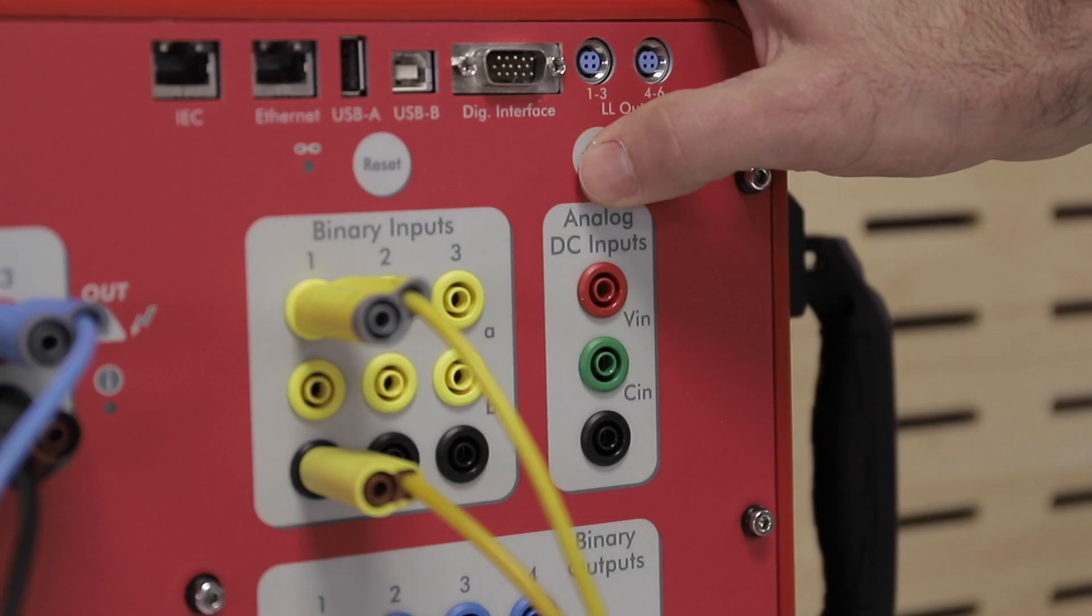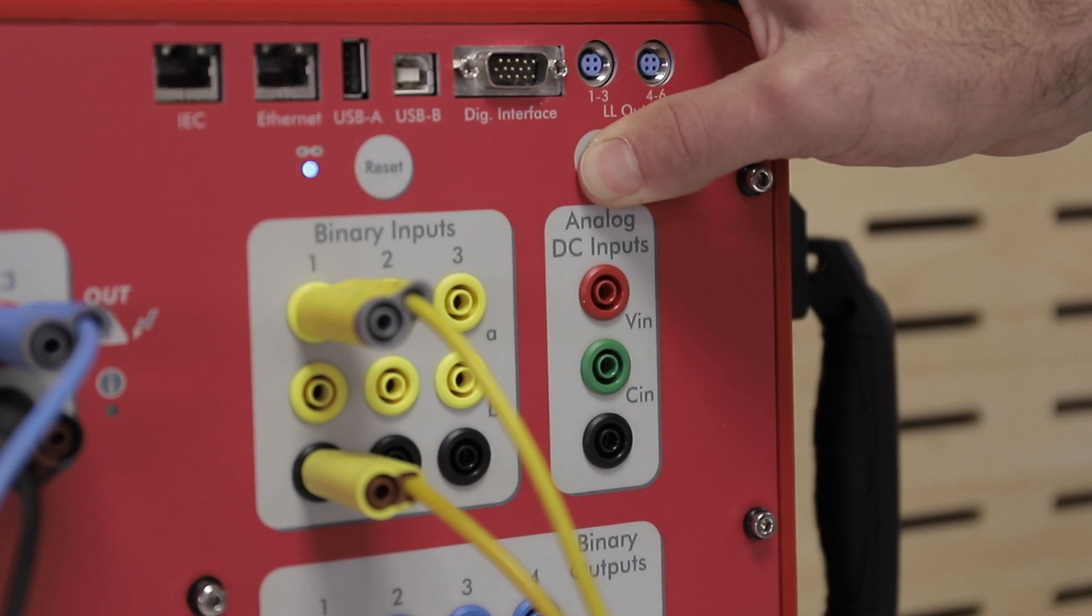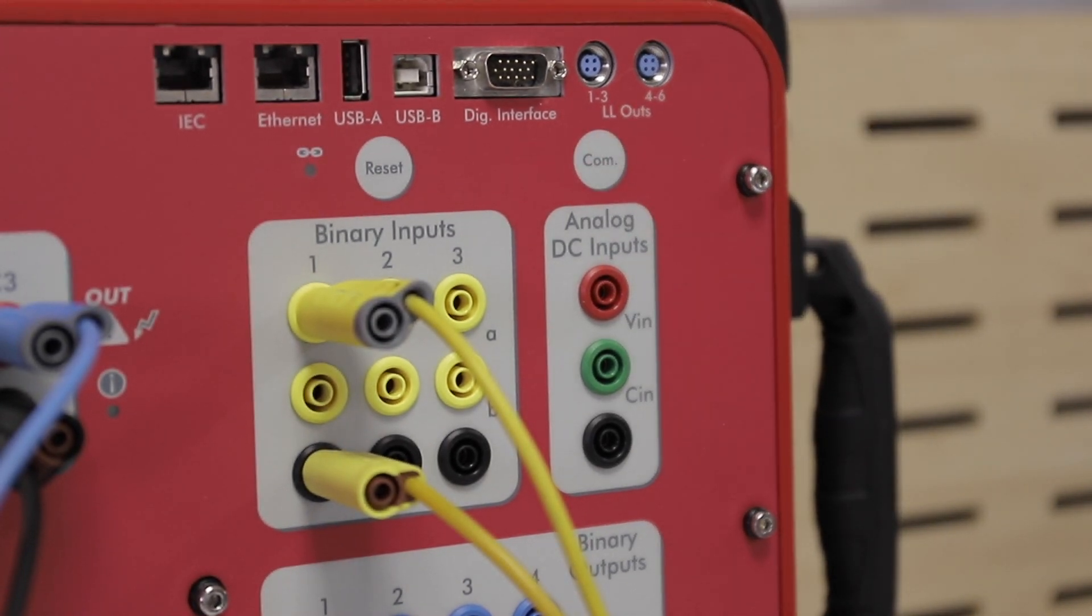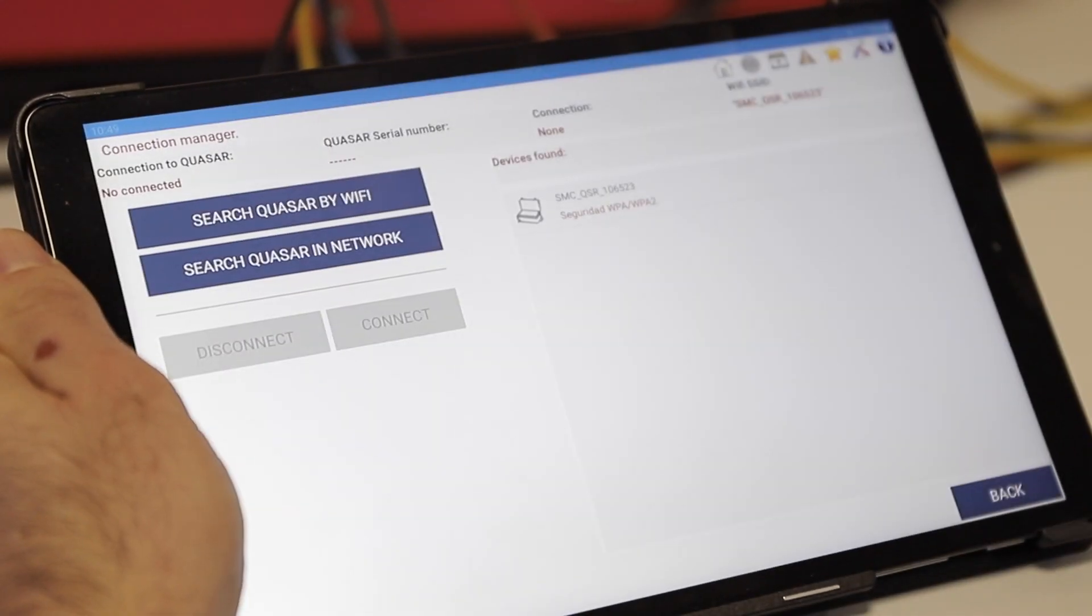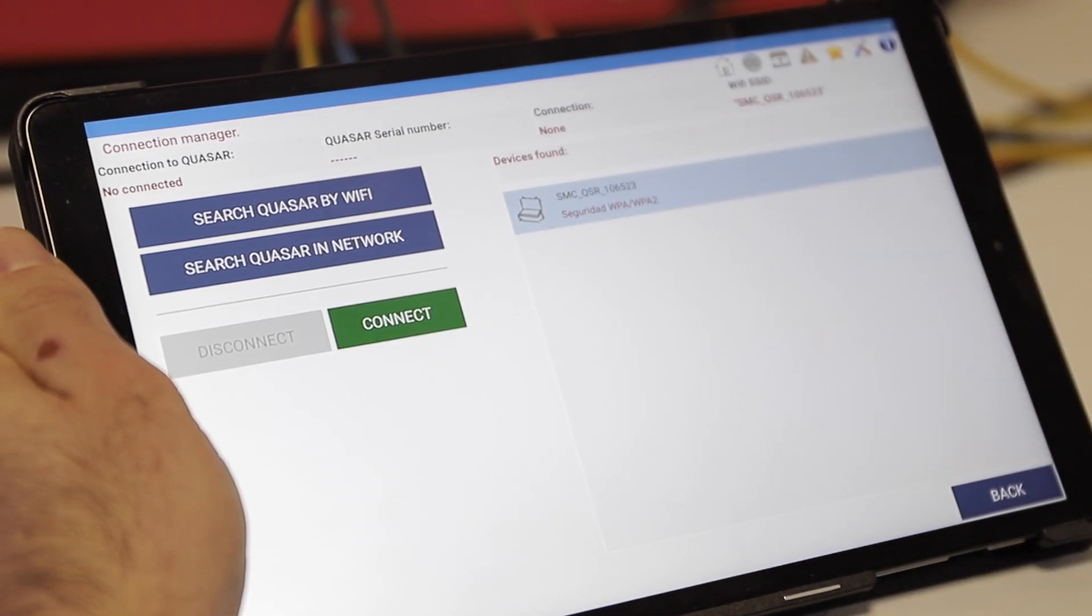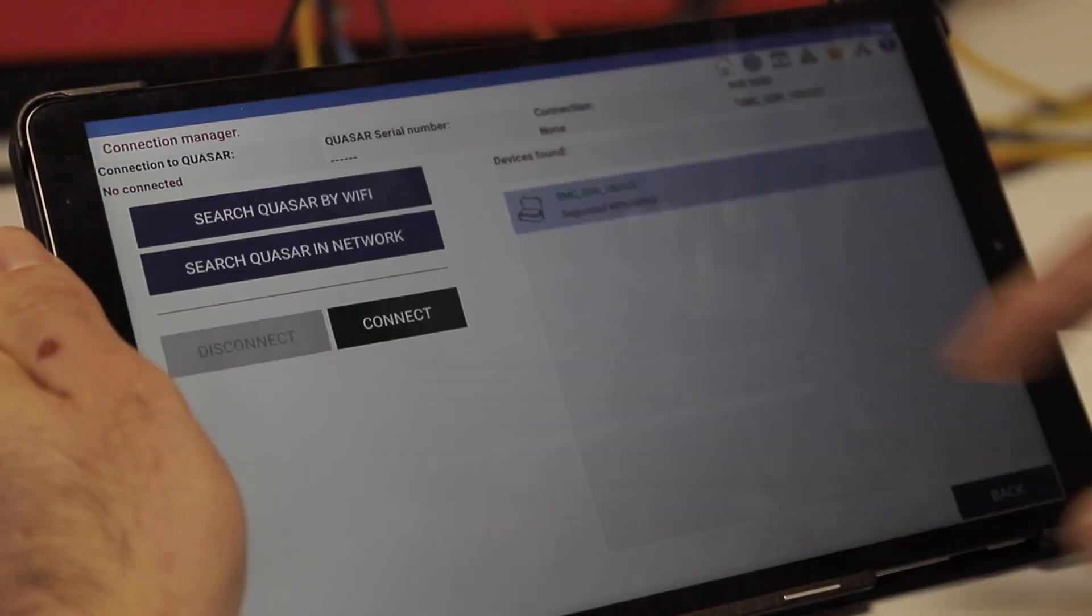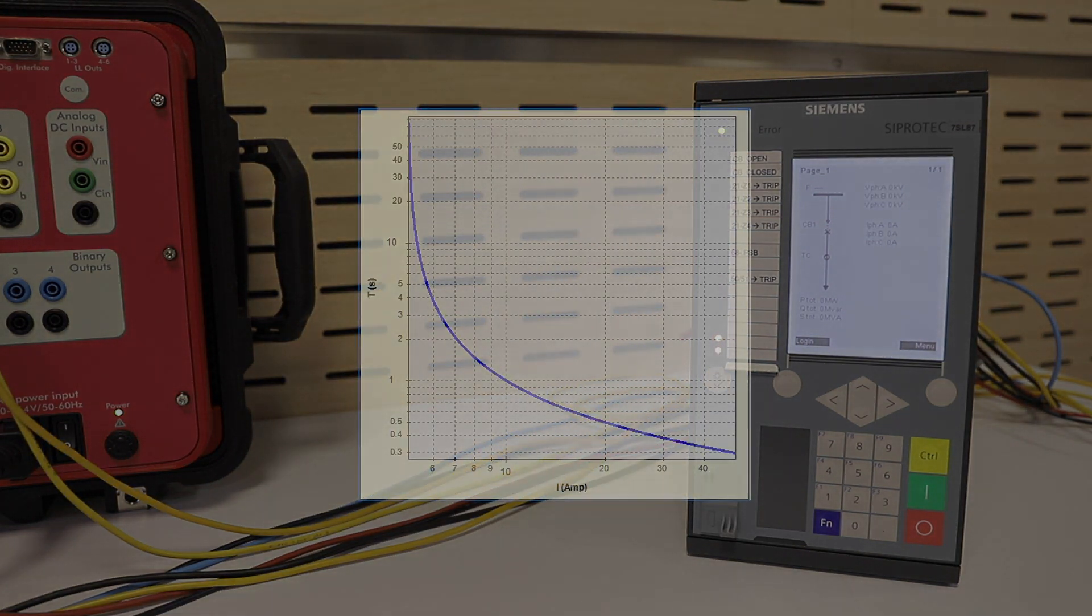In this part of the tutorial, we will use a tablet connected to the Quasar via Wi-Fi. We just need to locate the Quasar in the app and connect. According to the relay's trip characteristic, it will only operate if the injected current exceeds 5 amps.